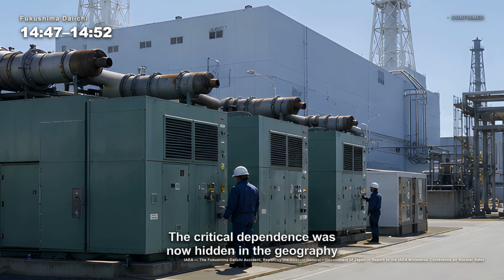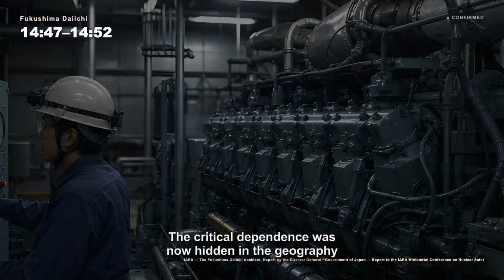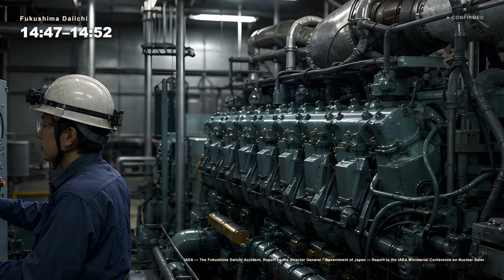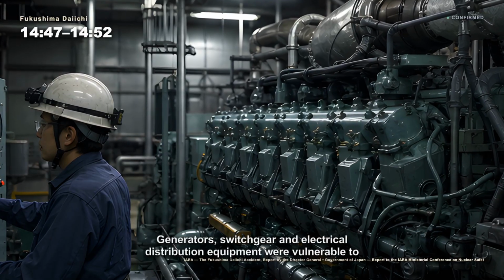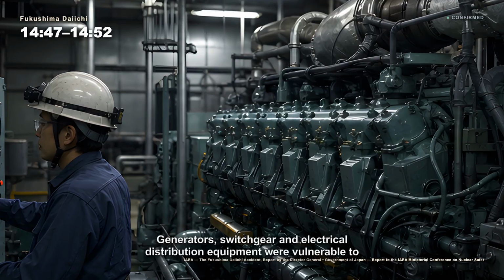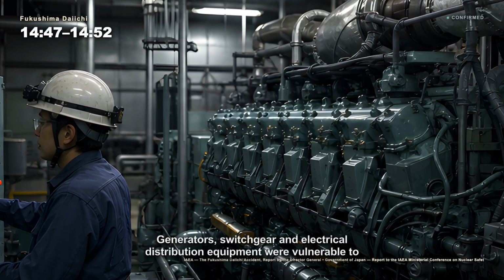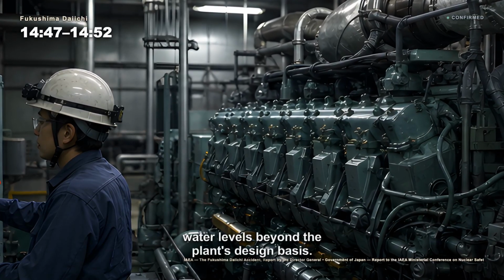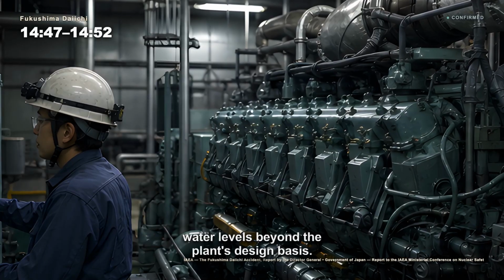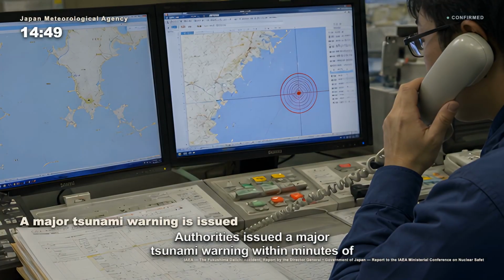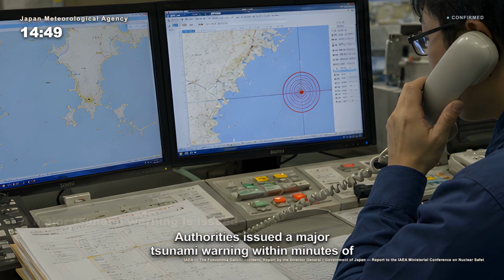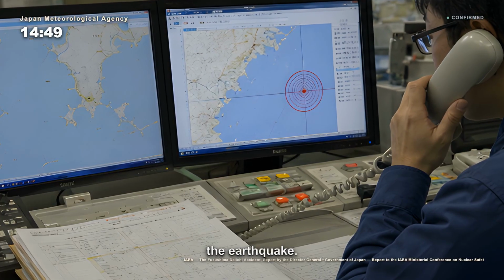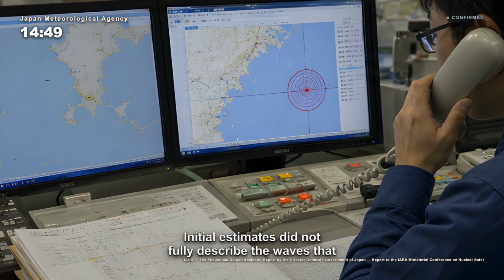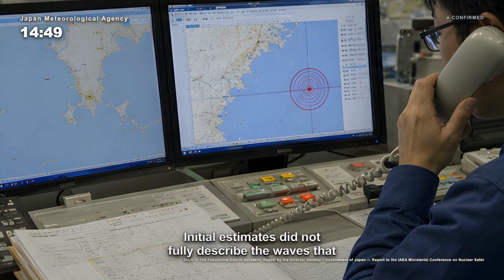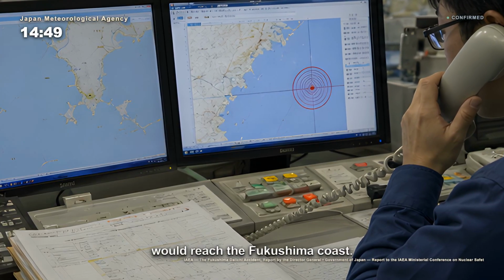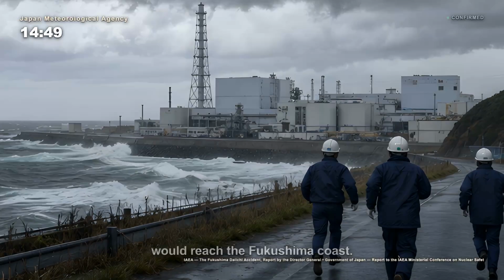The critical dependence was now hidden in the geography of the site. Generators, switchgear and electrical distribution equipment were vulnerable to water levels beyond the plant's design basis. Authorities issued a major tsunami warning within minutes of the earthquake. Initial estimates did not fully describe the waves that would reach the Fukushima coast.